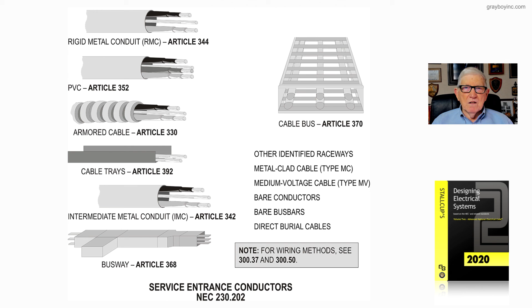Now, this figure 17-2 illustrates the wiring methods that you could use with service entrance conductors in accordance with NEC 230.202. And then, of course, we have the wiring methods selected for you, if you wanted to look at them very quickly: 300.37 if your high voltage system is installed above grade, and 300.50 if it's installed in the ground. And that's what this figure 17-2 is illustrating.